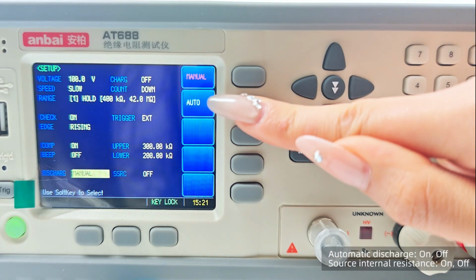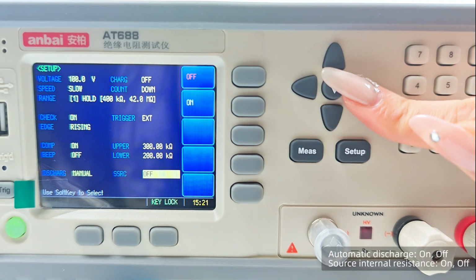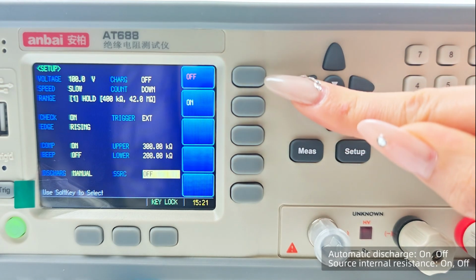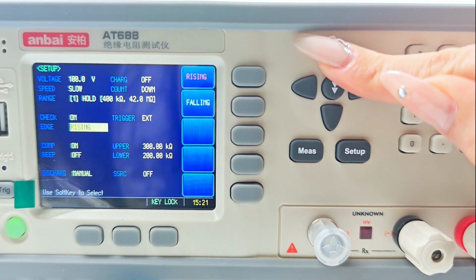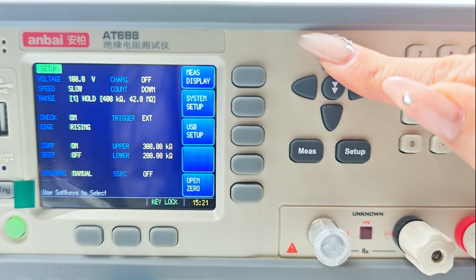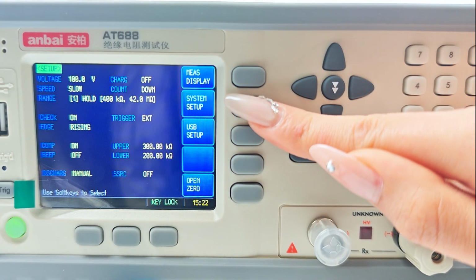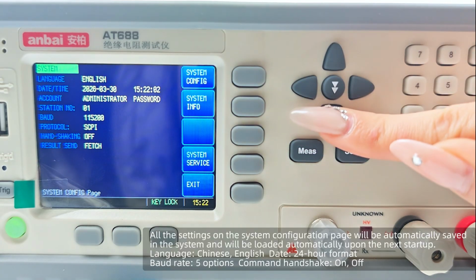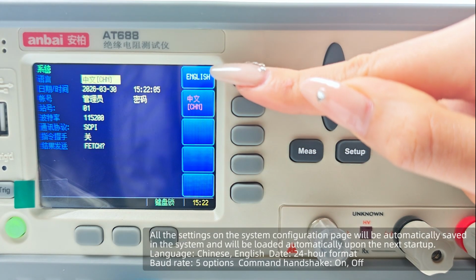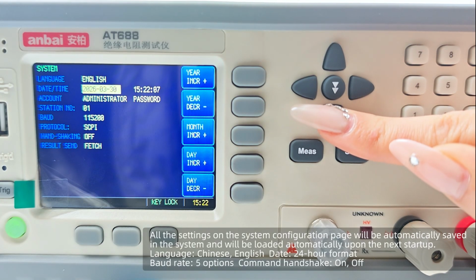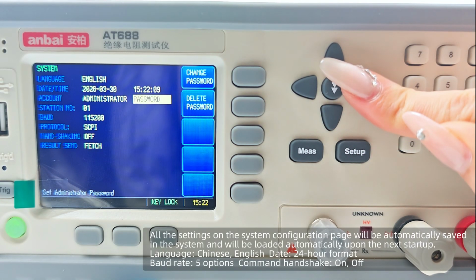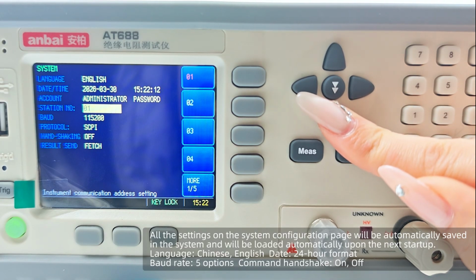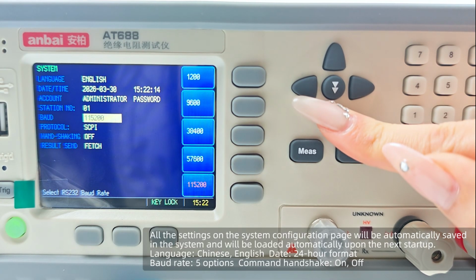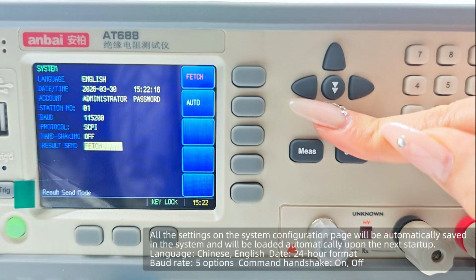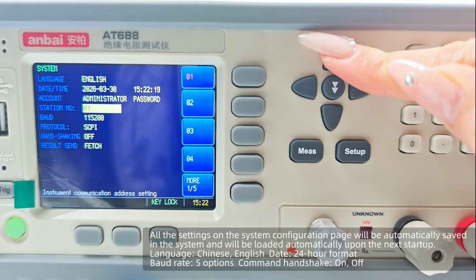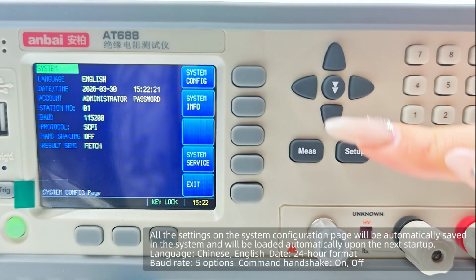When the instrument is in the testing mode, it takes one sample result, then automatically switches to the discharge mode, and the source internal resistance can be selected to be either on or off. On the main page of MEAS or Setup, click System Configuration to enter the System Configuration page. The System Configuration page includes the following settings: language, date or time settings, account settings, baud rate settings, command handshake, result sending. All the settings on the System Configuration page will be automatically saved in the system and will be loaded automatically when the system is restarted next time.